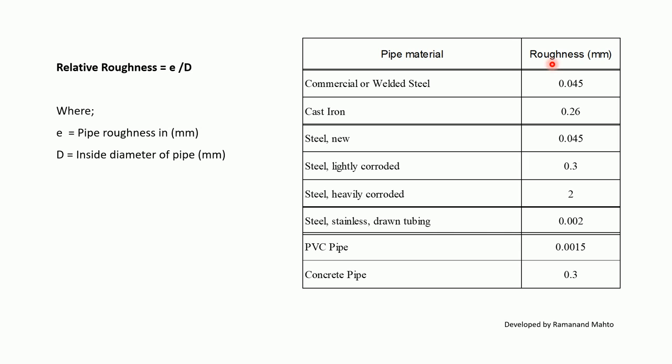Pipe roughness values by material: commercial or welded steel pipe: 0.045 mm; cast iron: 0.26 mm; steel new: 0.045 mm; steel lightly corroded: 0.3 mm; steel heavily corroded: 2 mm; stainless steel drawn tube: 0.002 mm; PVC: 0.0015 mm; concrete pipe: 0.3 mm.